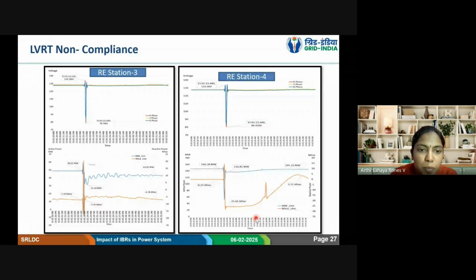The corresponding PMU plots are shown here, for RE station 3 and 4. Some megawatt loss and a delay in the megawatt recovery was observed. In this case it was an RB fault, so we are seeing a dip in the R phase and B phase voltages. Here we are seeing the megawatt and MVAr. During the fault, one is going high, the other is coming down, and it is getting recovered. In this case, it didn't recover at all. There was tripping. Immediately the inverters will trip and they have to restart. That restart didn't happen here.